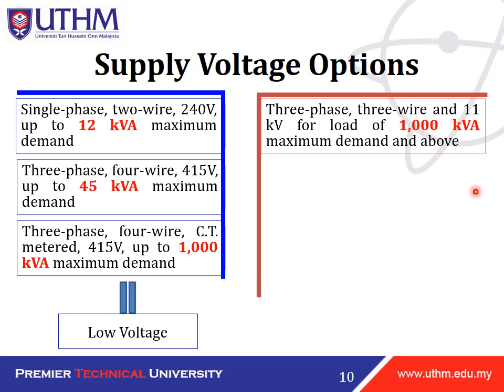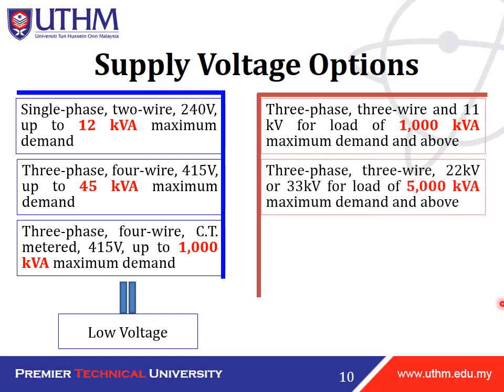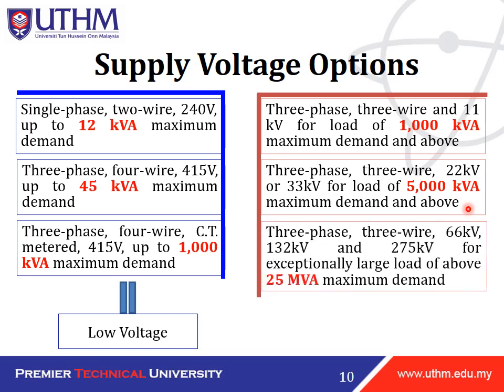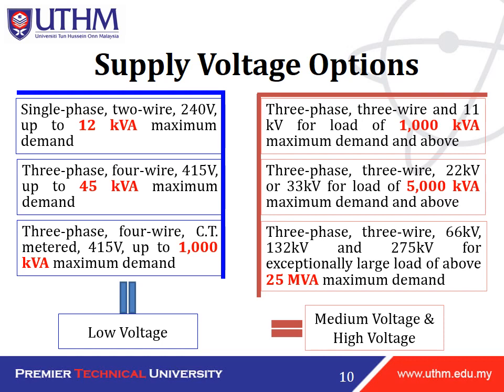And then we have three phase three wire 11 kilovolt for load of 1000 kVA maximum demand and above. And then we have 3-phase, 3-wire, 22 kV or 33 kV for load of 5000 kVA maximum demand and above. And then we have 3-phase, 3-wire, 66 kV, 132 kV and 275 kV for exceptional large load of above 25 MVA maximum demand. So this is the characteristic of medium voltage and high voltage.